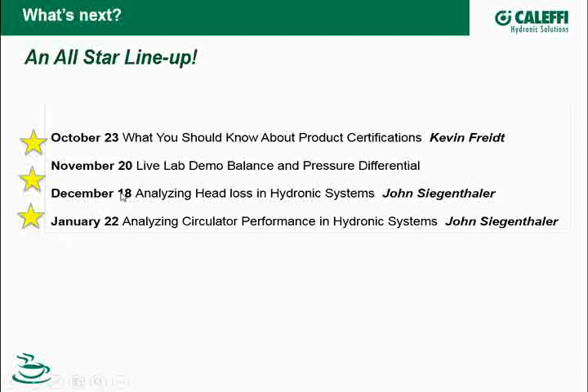December and January, I talked about this earlier. It's going to be a two-part one. Again, analyzing head loss on a hydronic system. This has to do a lot with pumps. We're going to look at how I tell what type of pump I need in the system if I don't think the right pump is in there currently, how I can do those calculations and analyze that, and then, of course, the circulator performance.